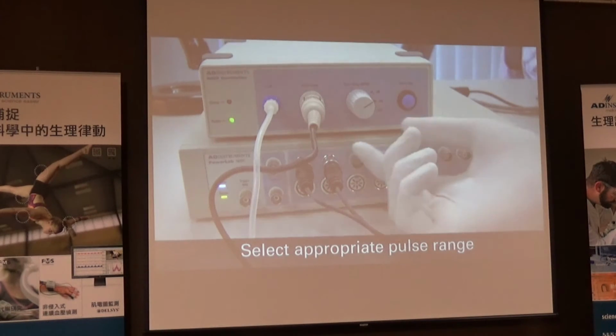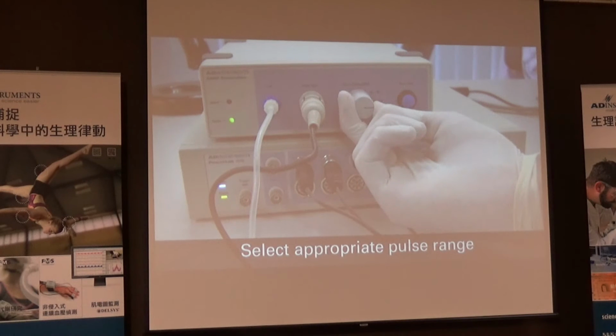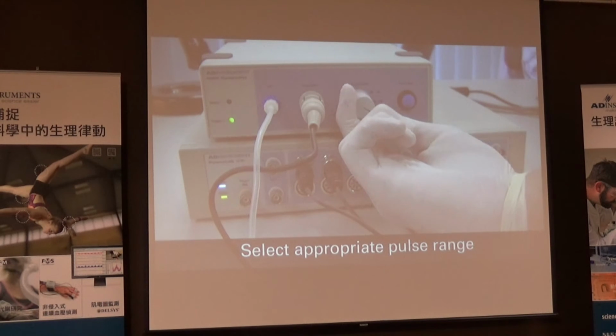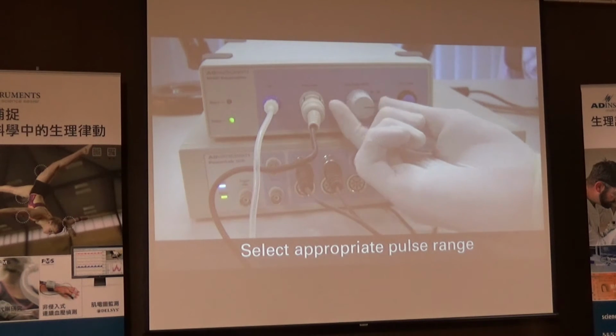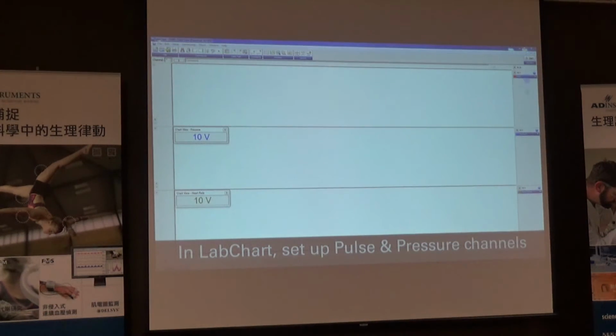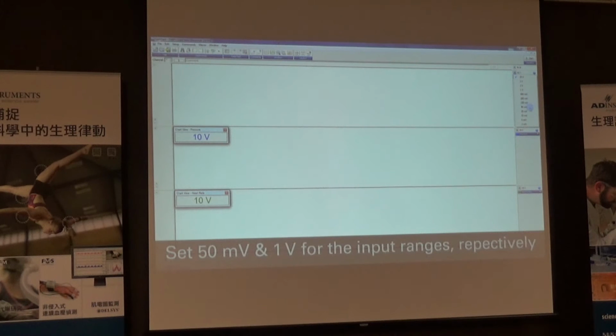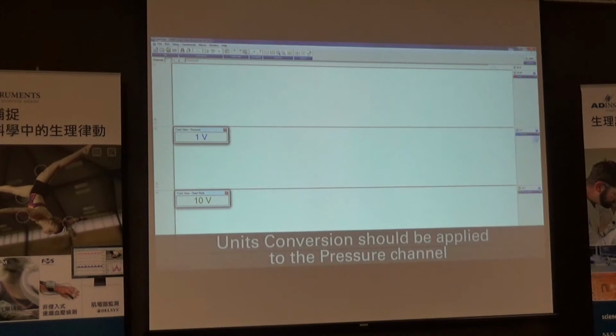Select the appropriate pulse range on the front of the NIBP controller. The maximum cuff inflation pressure can also be selected on the rear panel. In LabChart, set up two channels, one for the pulse signal and the other for pressure. You may also like to use cyclic measurements in the third channel to calculate heart rate from the pulse signal. The pulse channel range should be set to 50 millivolts, and the pressure channel range should be set to 1 volt.